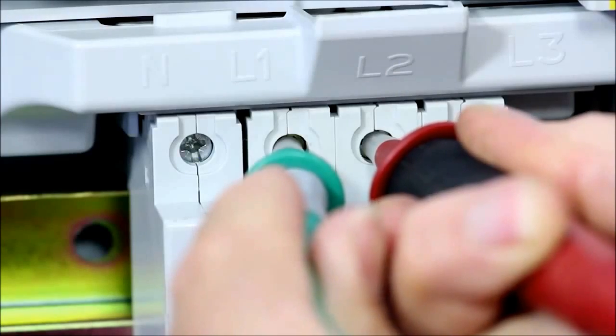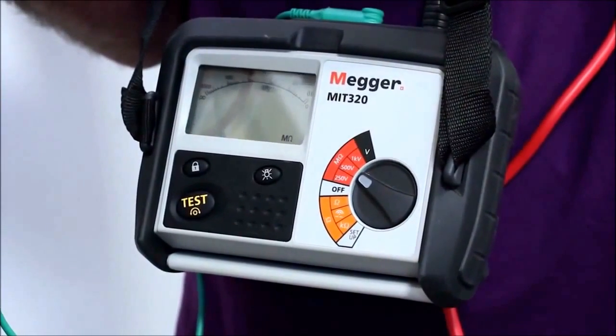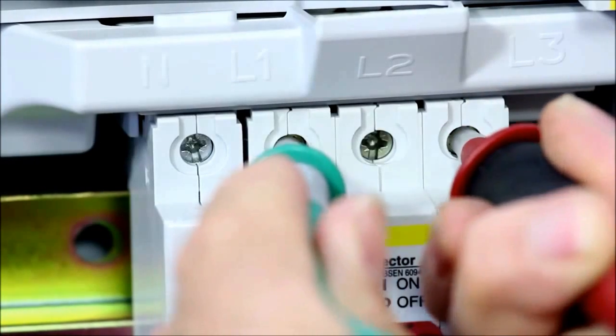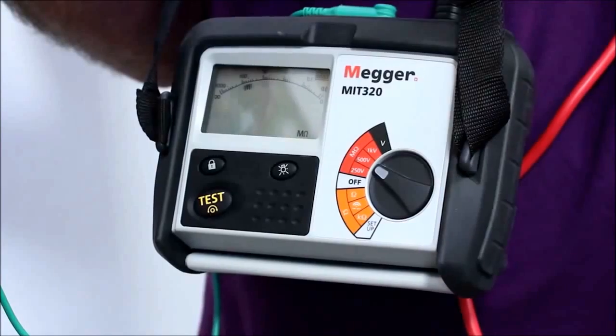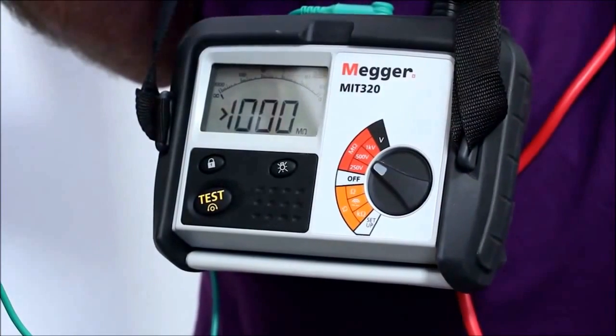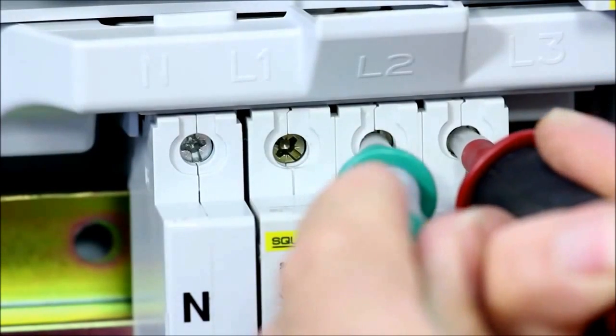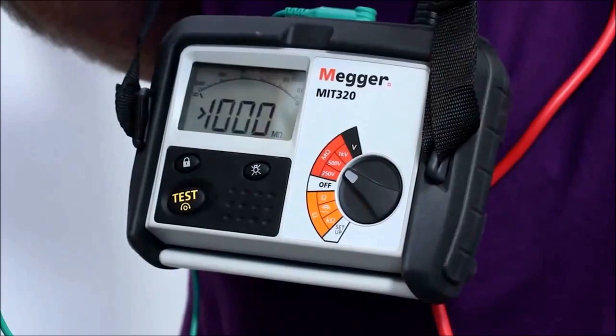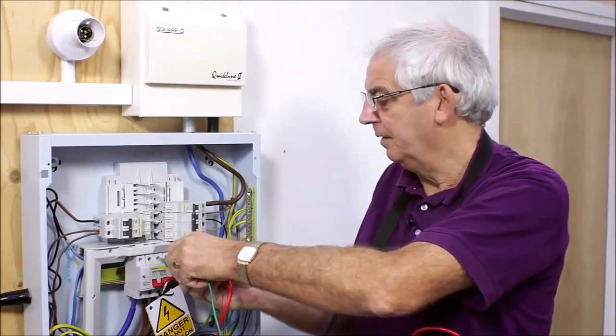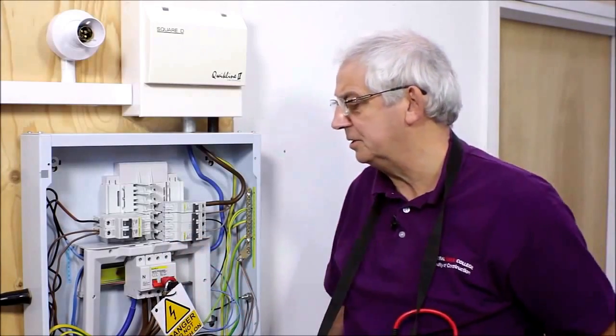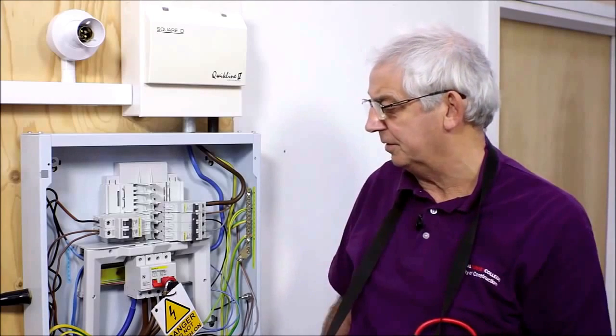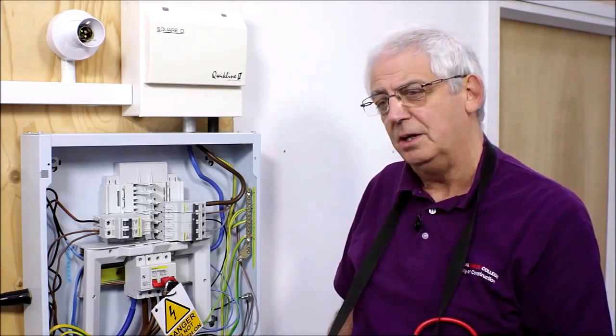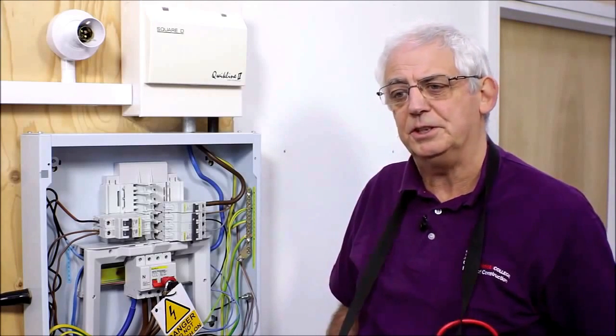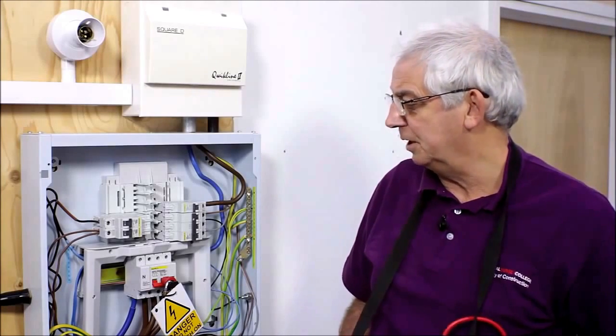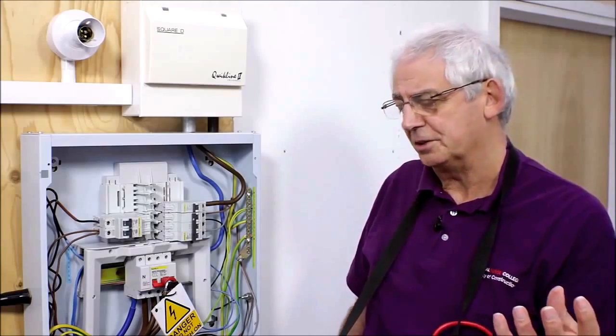L1 to L2, reading over range. L1 to L3, reading over range. L2 to L3, reading over range. And of course, while I was carrying out those tests, particularly the test between live conductors or line conductors and neutral, I should go around and operate any switches which may be controlling lights and devices, just to make sure that I'm testing the whole of the circuit.